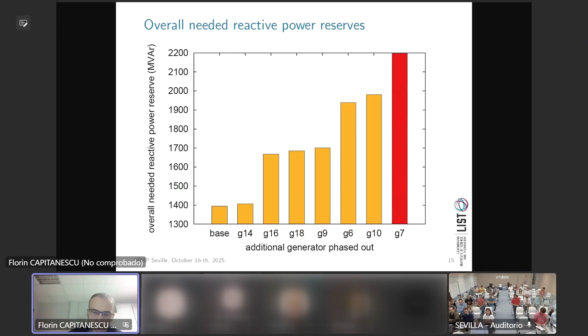Then at the solution of that, what is very important is that it actually gives you how much of the physical reactive power reserves is effective, and should receive remuneration, because for instance in one generator, like G14, okay, you may have, it even absorbs reactive power, but then it responds to contingency of that. This is the maximum that it gives across all contingencies at my optimum solution. So basically these orange areas are what is effective of the generators, but obviously this is only part of their physical capability. So the other is useless because basically it cannot help anymore to control voltages. Your system already experiences low voltages, and maybe it may go into a voltage instability. Okay, so that's another interesting concept, the concept of effective reactive power reserve.